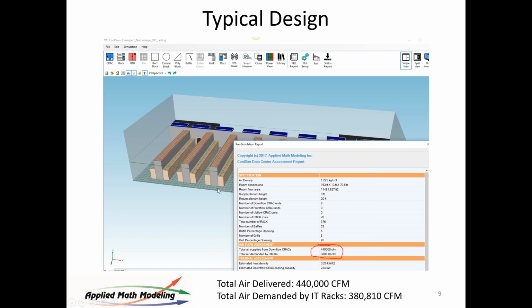And that's a sum, again, we're modeling here at average watts per rack. Early on in the design of a data center, you have no idea what's going in those racks. So average watts per rack works as well as anything because you don't know any better. We will show you later on how to dial that in tighter, but from the beginning, you don't really know what it is. And so you have to make some kind of assumptions.